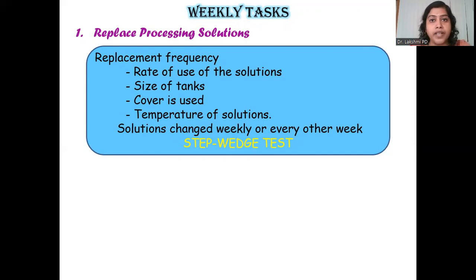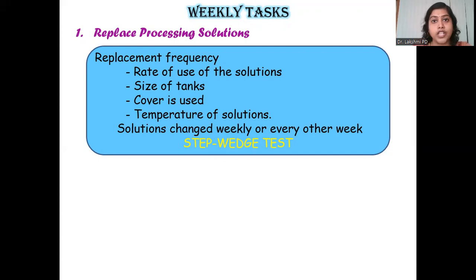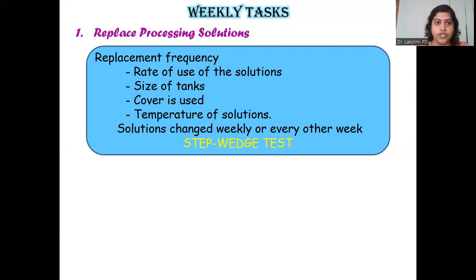The size of tanks also plays a major role: larger tanks allow processing solutions to be used for longer. Using covers is important, as oxidation by atmospheric oxygen can lead to depletion. If covers are properly replaced after every use, it can prolong the time before replacement is needed. Ultimately, your step wedge test or reference films will tell you when it is time to replace your processing solution.